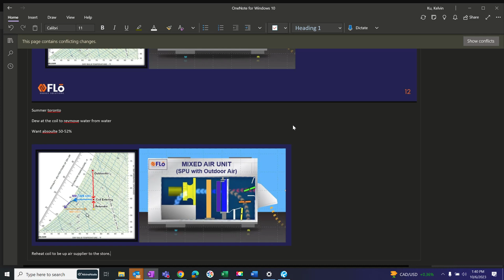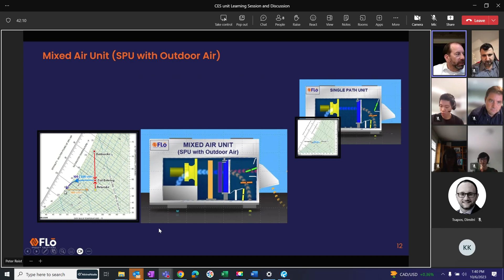So if you just look at some of these values, it looks like the incoming air is at about 58 dew point, because it's just a little bit below the 60, since these are the dew point numbers there. And then in this psychrometric chart, the unit is driving that air down to 54 dew point, and then it's reheating it, and it's still at 54, right? So 54 isn't acceptable, is it? We said that what we really want is 50 to 52.